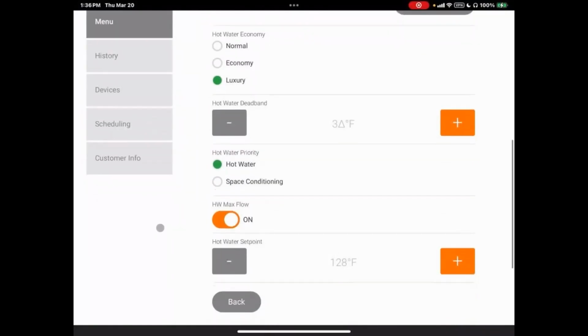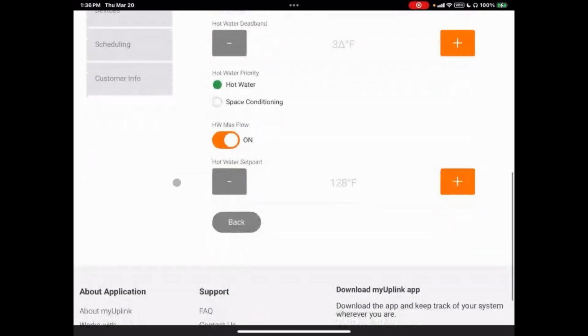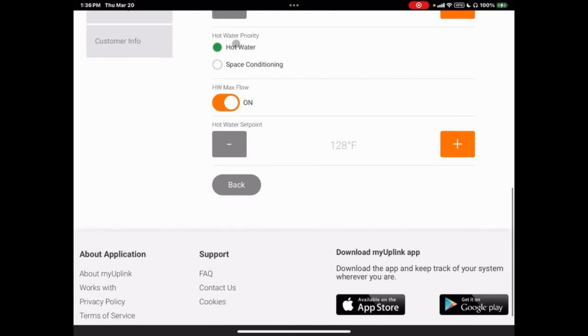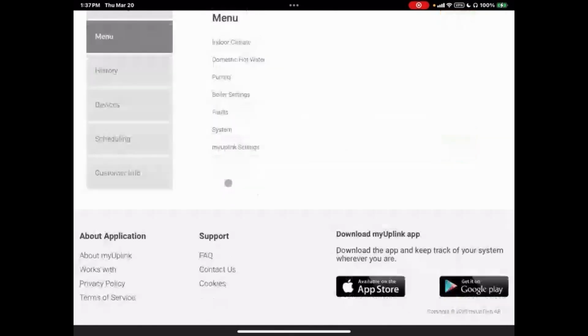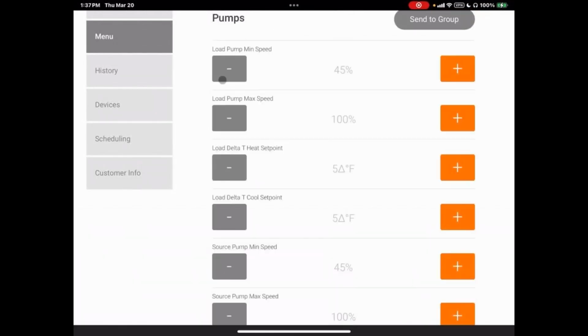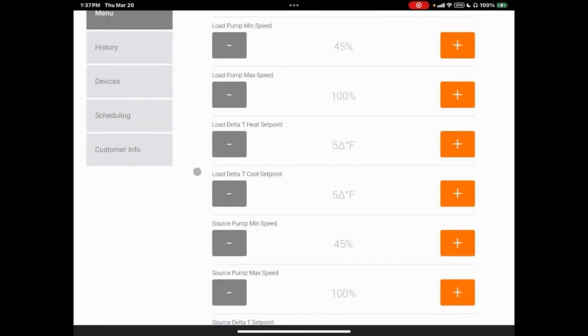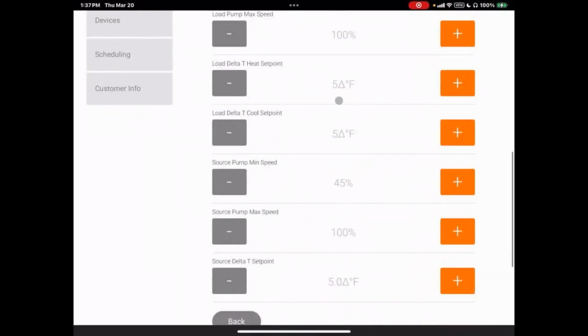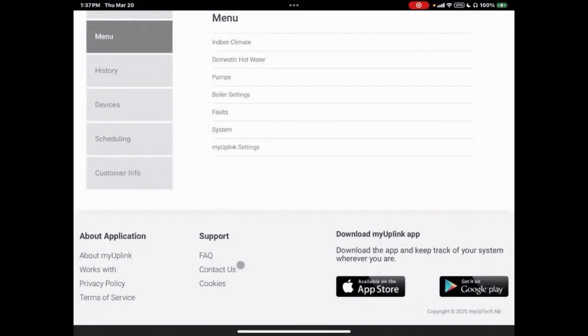This is the domestic hot water settings. You can see we have normal, economy, and luxury settings for the hot water. Again, we can choose between priorities on hot water or space conditioning. When it comes to our pump settings, we can change minimum and maximum speed on the load pump, as well as on the source pump, as well as the delta Ts on each side, source and load. Here we have the delta T for the heating mode and one for the cooling mode on the load side, and then a delta T set point for the source side. On this particular unit, they're all set at 5 degrees, but those are adjustable, so you can configure it for your project.